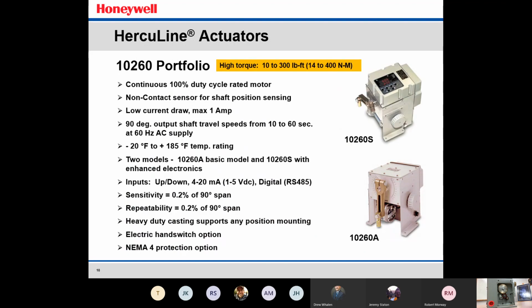So let's talk a little bit more about the 10260. We'll take a little bit deeper dive into this product. Again, 10 to 300 foot-pounds of torque, continuous 100% duty cycle. So this is very, very important when you're in ambient temperatures that are in excess of 100 degrees and upwards. A lot of the actuators that are not rated for industrial climates have braking mechanisms in them. Those braking mechanisms will deteriorate over time with excess ambient temperatures. So those become less of a 100% duty cycle and probably somewhere around 50% duty cycle after a period of time.